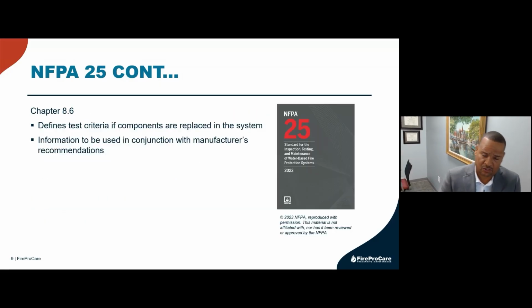Chapter 8.6 talks about the components in the system. If you ever have to change something in that system, it kind of tells you what you need to do from an interval standpoint and from a testing standpoint if you modify something. Information is also supposed to be used in conjunction with the manufacturer's recommendation. So again, that word keeps popping up in my presentation because manufacturers, when it comes to the controllers, have never had any recommendations, at least not well documented or anything that's published. Today that exists, and we need to make sure the market is aware of it. The industry is aware that you need to follow those recommendations.